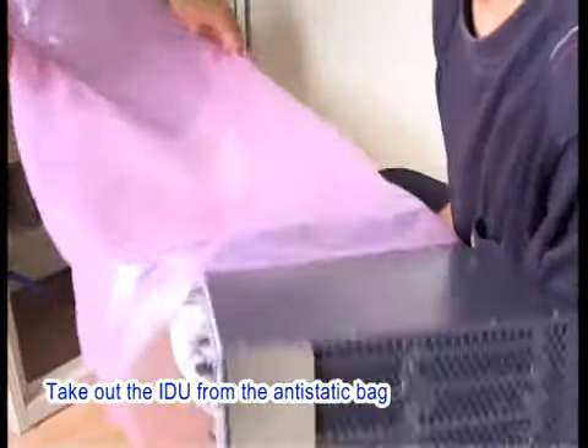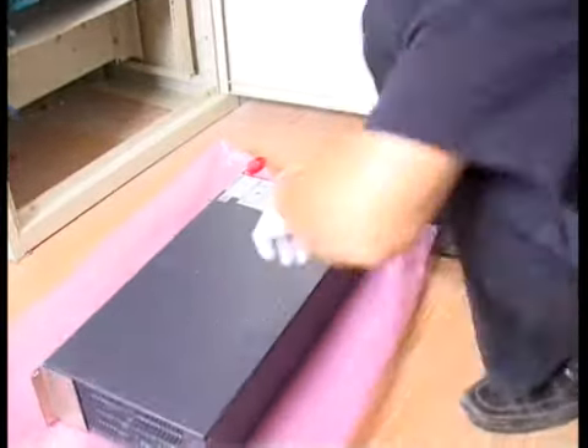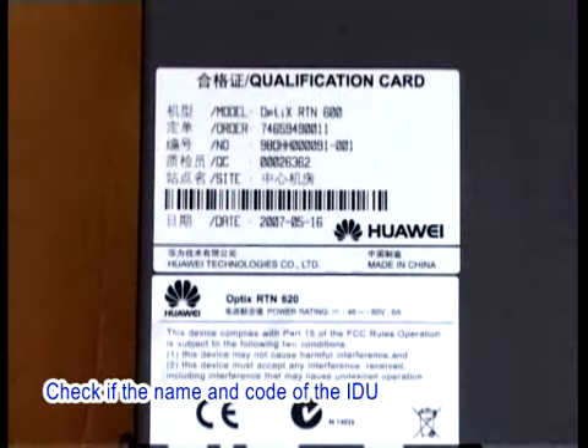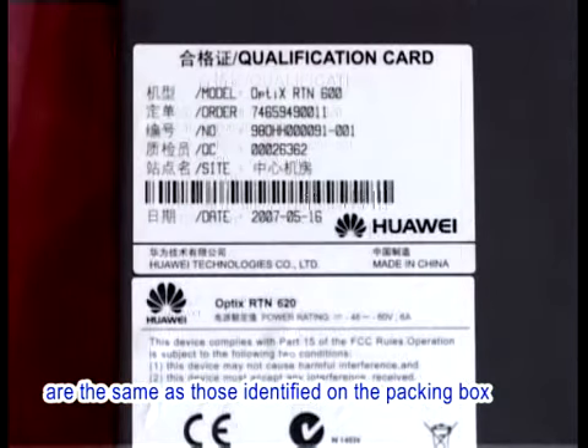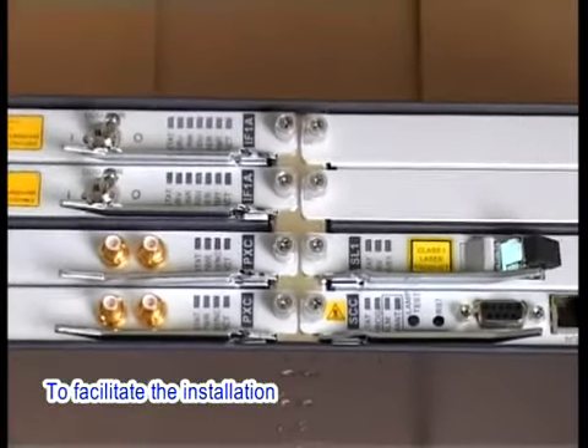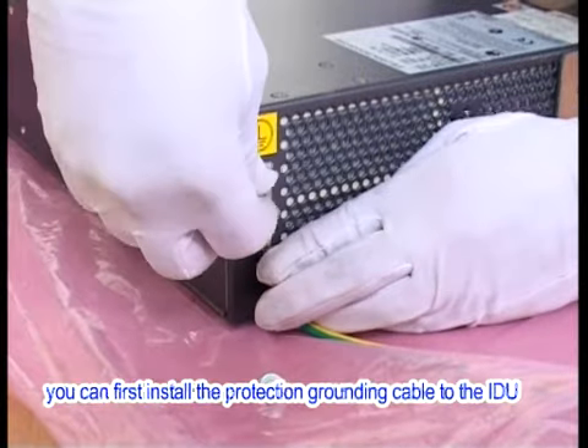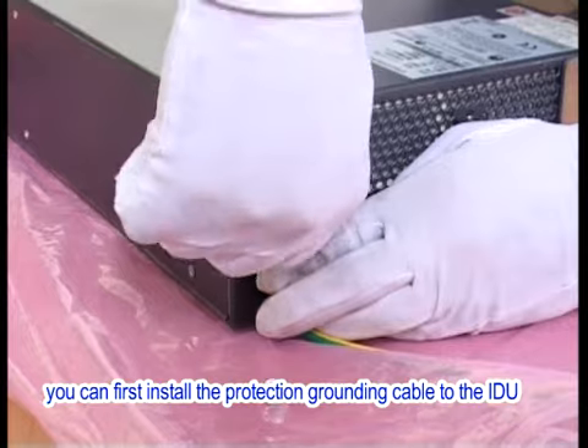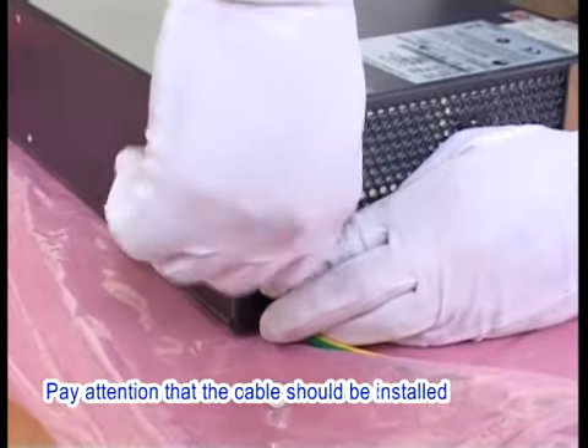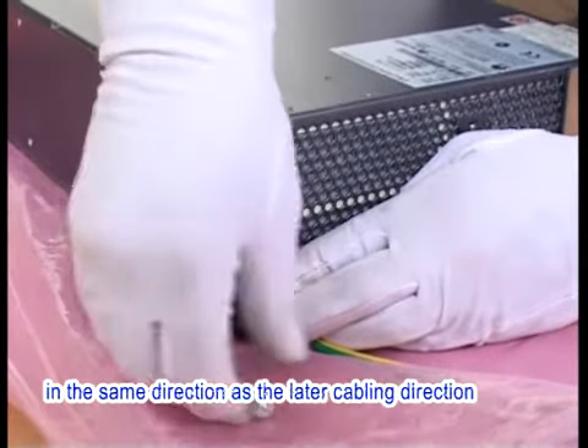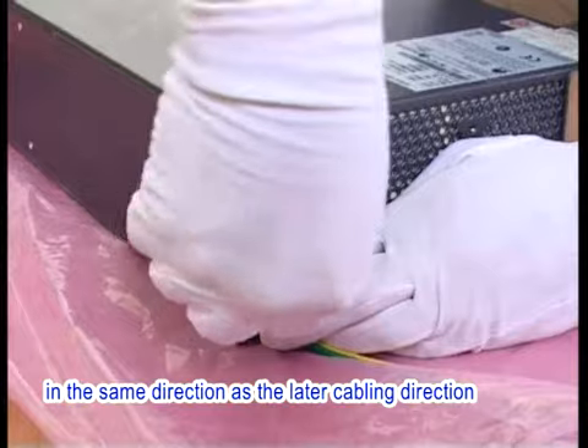Take out the IDU from the anti-static bag. Check if the name and code of the IDU are the same as those identified on the packing box. Check if the IDU is intact. To facilitate the installation, you can first install the protection grounding cable to the IDU. Pay attention that the cable should be installed in the same direction as the later cabling direction.